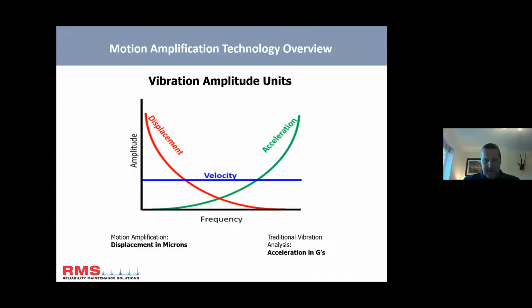Some of you guys in vibration may have seen this graph, where the camera sits is the red line. Its native unit is displacement, and displacement is more enhanced at the lower frequencies. So this technology isn't designed to look for high frequency bearing defects, gear defects, or lubrication problems. It's designed to look at the lower end. So if you've got a high running speed vibration, twice running speed, maybe some blade passes or pulsation frequencies, we can see that with the camera. This is what it's designed for.